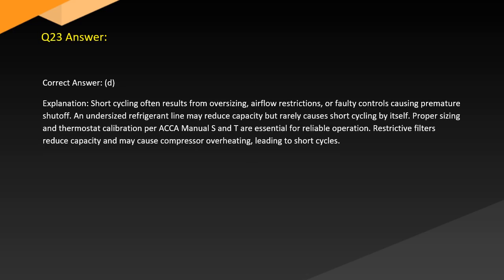Answer. Correct answer, D. Explanation. Short cycling often results from oversizing, airflow restrictions, or faulty controls causing premature shutoff. An undersized refrigerant line may reduce capacity but rarely causes short cycling by itself. Proper sizing and thermostat calibration per manufacturer manuals are essential for reliable operation. Restrictive filters reduce capacity and may cause compressor overheating, leading to short cycles.